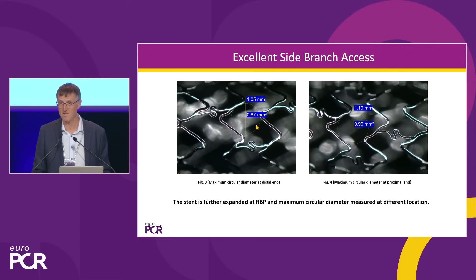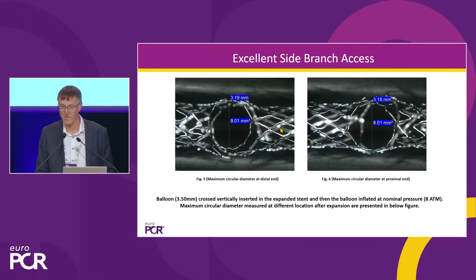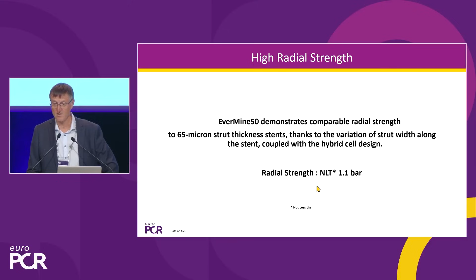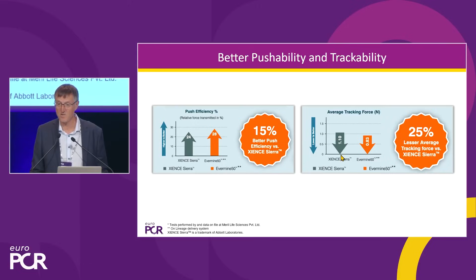You can also see on this picture that you have the closed cells. So this is one thing you have to learn when you use this stent. You don't want these ends of the stent to cross an important side branch because these are difficult to open. We have these closed cells to prevent longitudinal compression of the stent and also to achieve good radial strength when we implant it in ostia. The EverMine50 stent also demonstrated very good radial strength compared to the 65 micron strut stents. The radial strength is not lower than 1.1 bar, and it has 15% better push compared to the comparator, and the tracking is also less than the comparator.